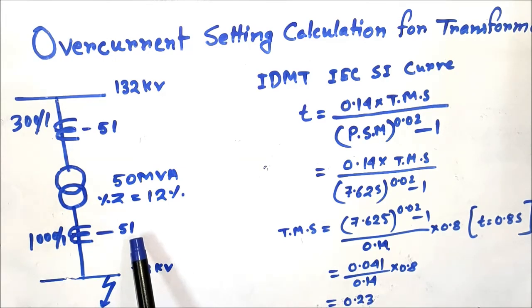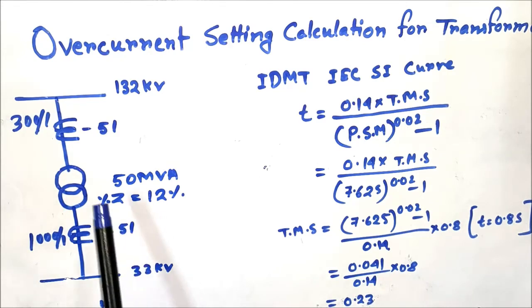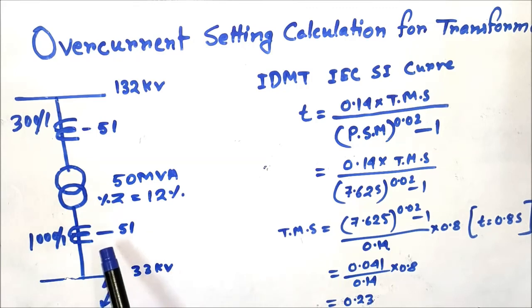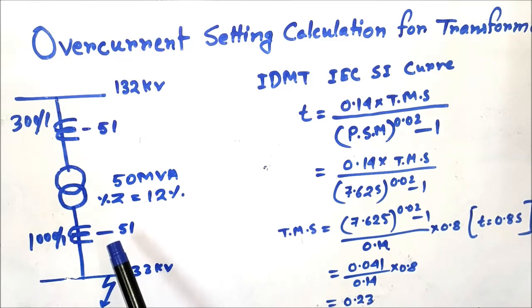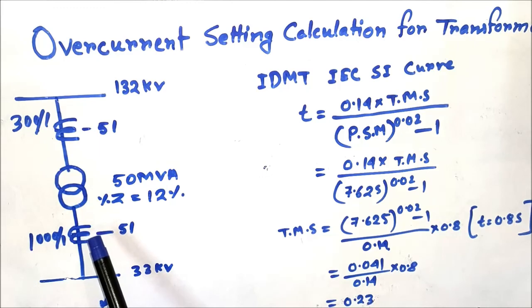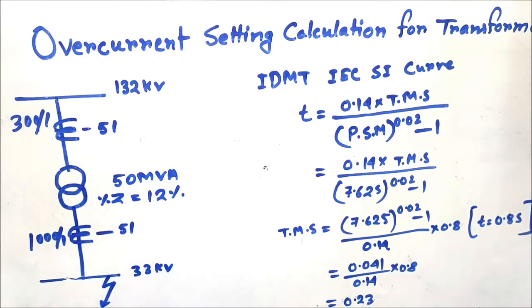To summarize: the TMS for the LV overcurrent relay is approximately 0.18, and for the HV overcurrent relay it is 0.23. The current set should be 110% of full load current for both LV and HV sides. This is how we calculate the overcurrent relay settings for LV and HV relays on transformers. If you liked the video, please subscribe to my channel and press the bell button for notifications. Thank you for watching.